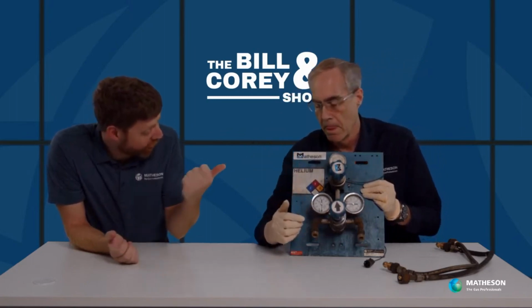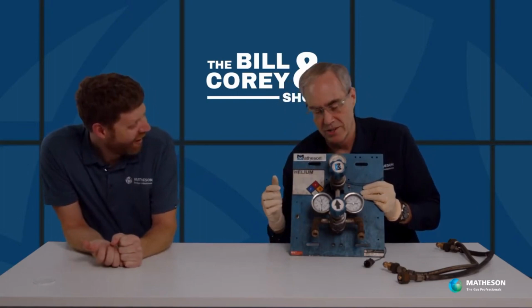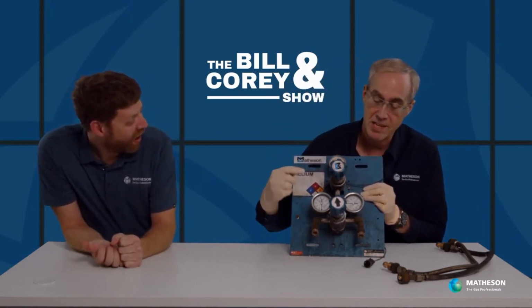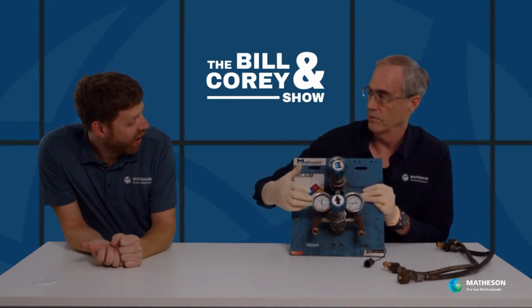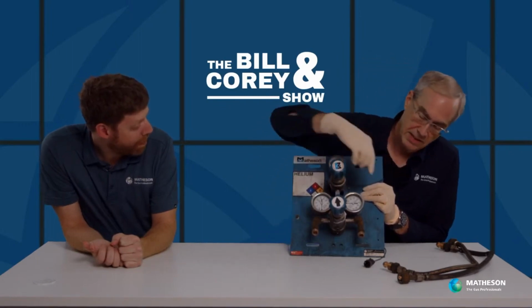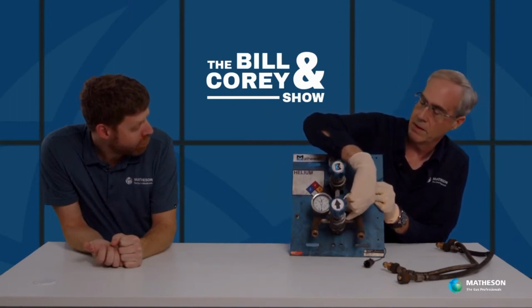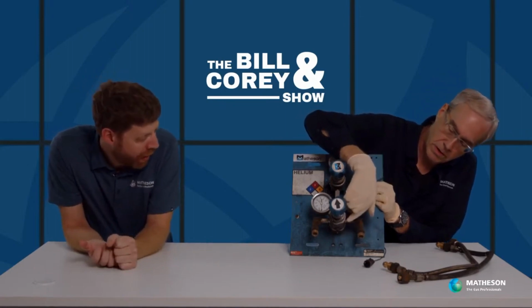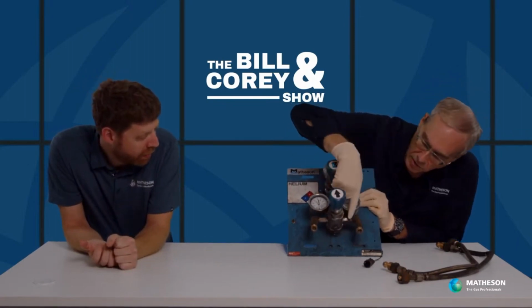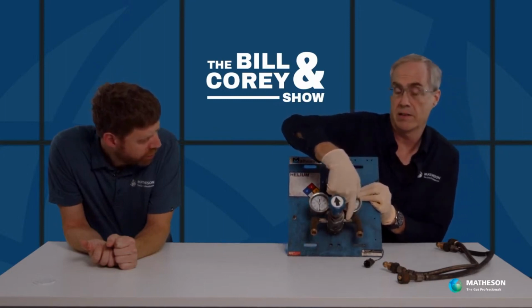So what happens, Bill, if there's no relief valve on there? Well, we would probably put one in there. But the reason I'm bringing it up on the show is not just that someone wants to refurbish things. It's the fittings they put on. If they order without hoses, they're just going to get maybe an elbow on the inlet. They put on their own piping, and they have a little stainless steel hex nipple in there. That looks like it's rated to cylinder pressure.